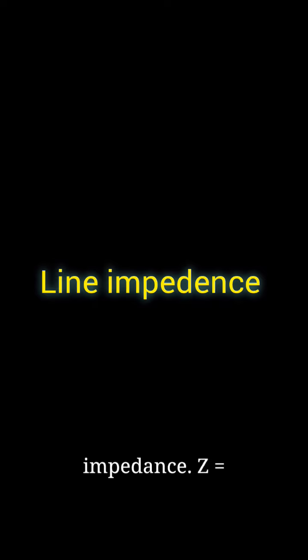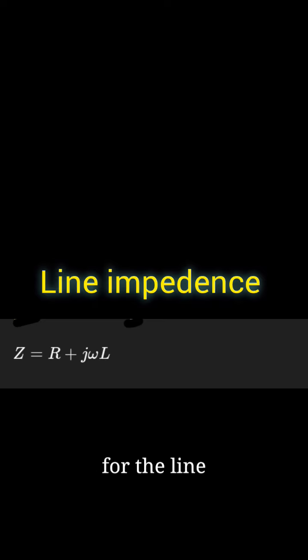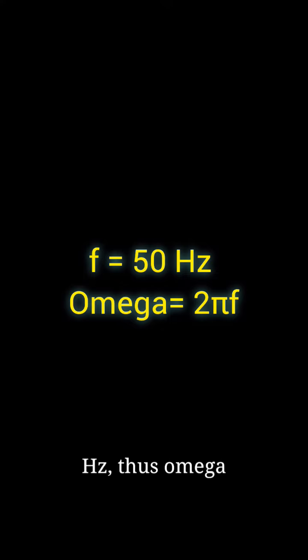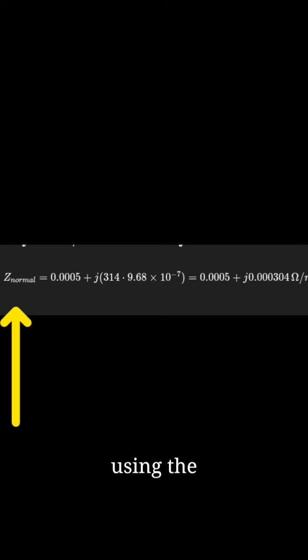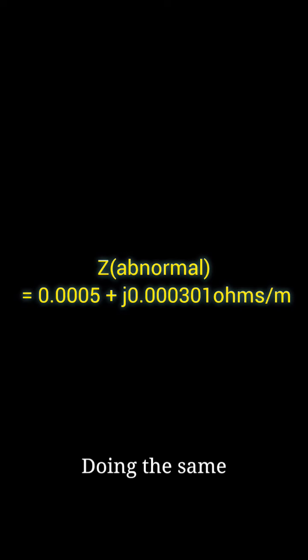Line impedance Z is equal to R plus j omega L, which is the formula for the line impedance in the transmission line, as we all know. Let's say R, the resistance, is equal to 0.5 ohm per kilometer, so 0.0005 ohm per meter, and the frequency is equal to 50 hertz. Thus omega is equal to 2 pi f, which is about 314. Now the normal impedance, using the formula, we will get 0.0005 plus j 0.000304 ohm per meter. Now let's go for the abnormal line impedance. Doing the same, we will get 0.0005 plus j 0.000301 ohm per meter.